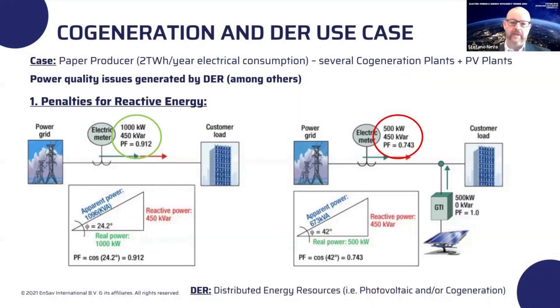For example, the problems that we solved for this company: first of all, we reduced to zero the penalties for reactive energy. Because they have large photovoltaic plants, they have a problem with a reactive energy penalty. This is created by the fact that photovoltaic plants create energy with a power factor of 1, so it doesn't need any power factor correction.